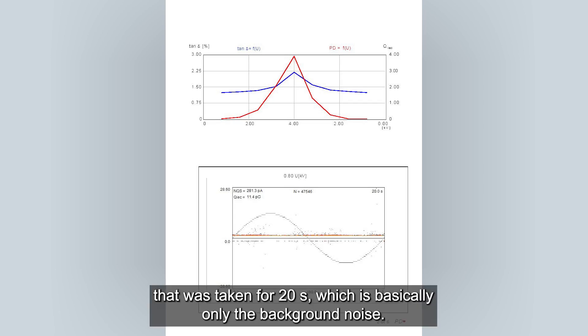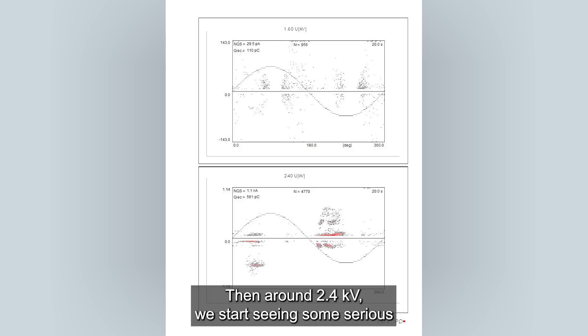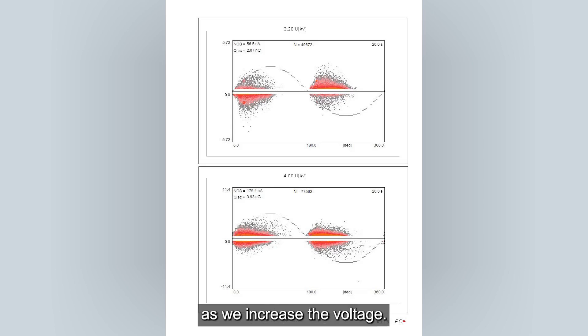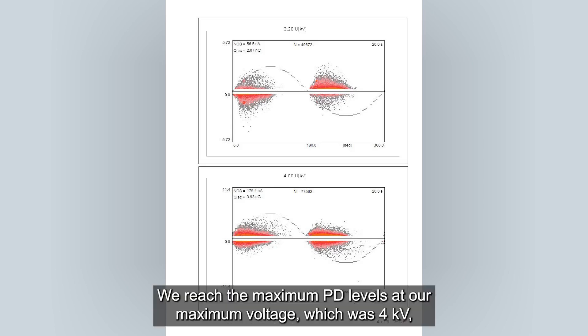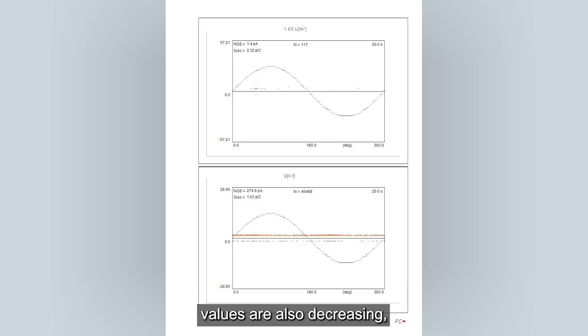Then we see PRPD at each voltage level. Then around 2.4 kV, we start seeing some serious partial discharge signals which increases as we increase the voltage. We reach the maximum PD levels at our maximum voltage, which was 4 kV. And as we ramp down the voltage, we see the PD values are also decreasing until we get back to our background noise.